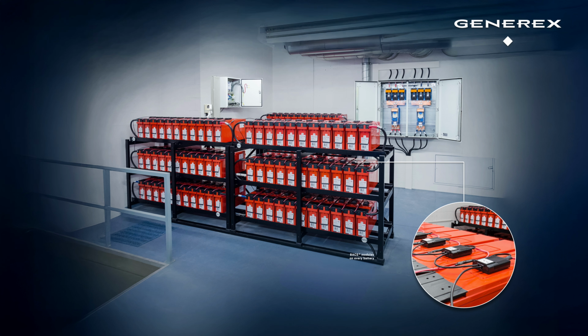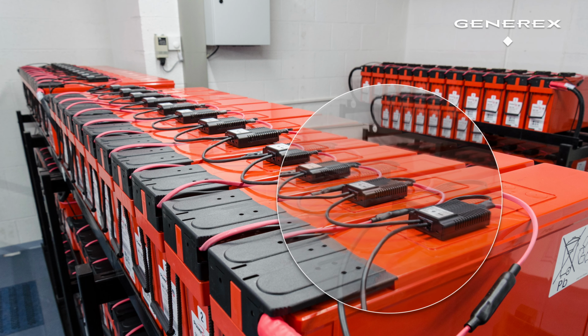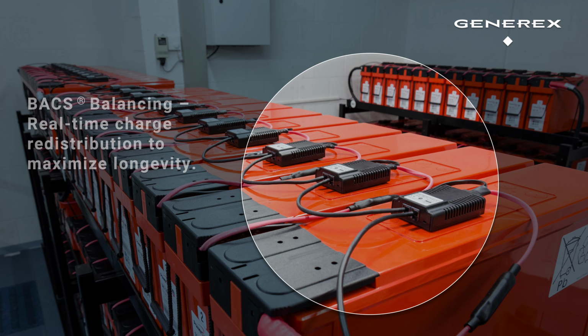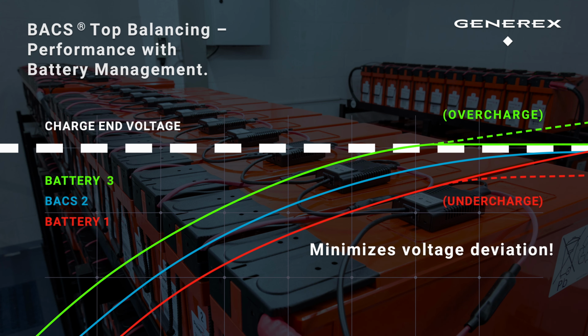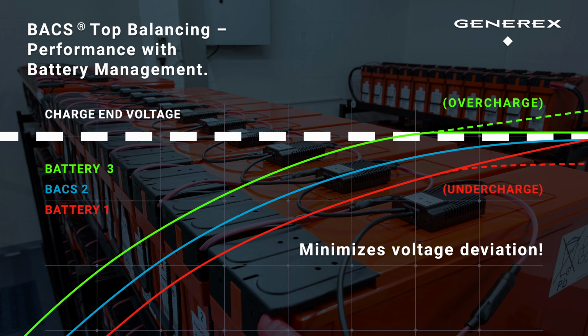Here you can see the BACS modules of the classic and the new line placed on the battery top side with the red and black measuring cables to the battery poles. The current sensors are required for battery capacity measurement and discharge detection and have Hall sensors designed as a ring that can simply be opened up for assembly.